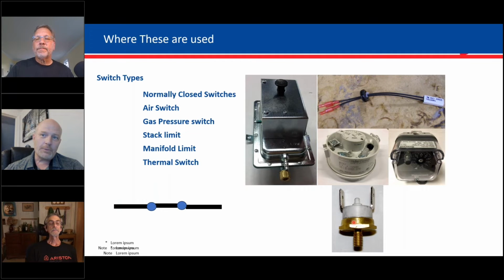Down in the bottom of the screen here, we've got a newer addition to some of the products. For those of you that do LXs, you will have seen some of these on the burner doors. This was recently added to the FTVN boilers, and it's attached to the burner door as well. It's a high temperature manual reset thermal limit. And again, it is normally closed, and it opens upon temperature rise. So if it gets too hot, it opens.